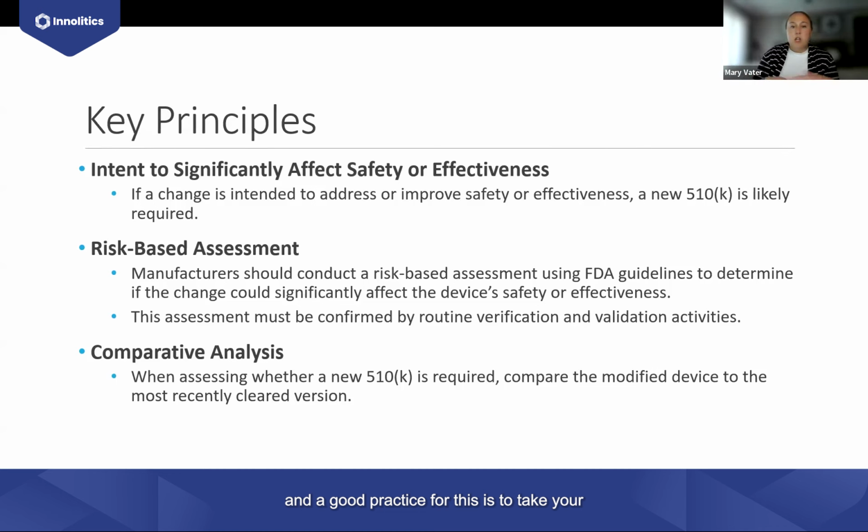And a good practice for this is to take your risk analysis and identify which of the risks identified in your risk analysis apply to the change that you're making, or which of those risks could be impacted by the changes you're making, and reference those risk IDs and reference that evaluation and assessment that you're making for basing that decision.